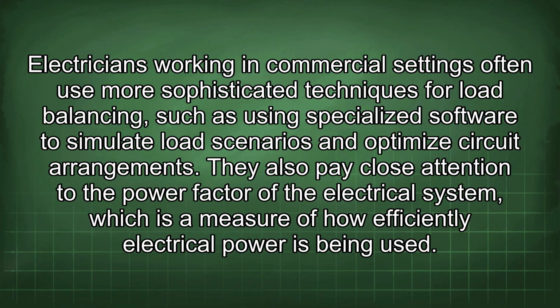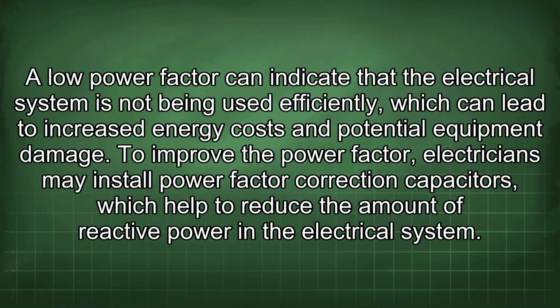They also pay close attention to the power factor of the electrical system, which is a measure of how efficiently electrical power is being used. A low power factor can indicate that the electrical system is not being used efficiently, which can lead to increased energy costs and potential equipment damage. To improve the power factor, electricians may install power factor correction capacitors, which help to reduce the amount of reactive power in the electrical system.